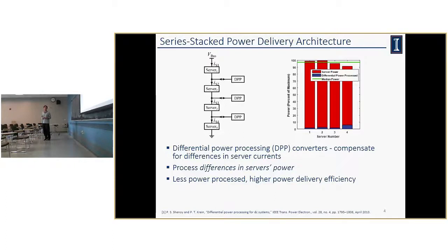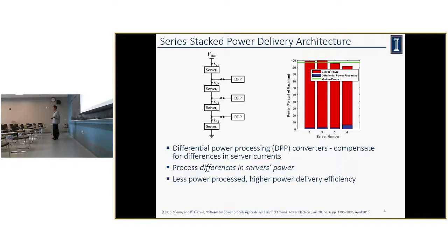In reality, server power is not identical, so we introduce differential power processing to solve this problem. We can have bidirectional DC-DC converters called differential power processing (DPP) converters to compensate for the difference in server current, connected at the intermediate nodes between servers. These DPP converters only process the difference in server power — not the full server power — so the power going through them is much less, the power lost is much less, and we can achieve extremely high efficiency. A comparison plot shows the blue bars (differential power) are much smaller than the red bars (full server power).